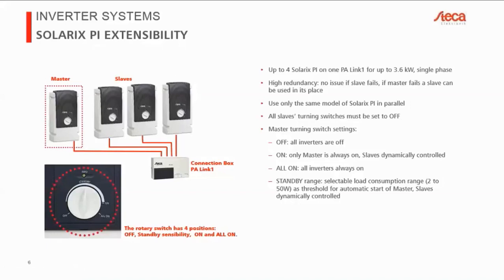Of course, the downside of having all the inverters running all the time is that you will have the no-load consumption of all the inverters as well. So if each converter is taking 6 watts, for example, then you have 24 watts of consumption because all 4 are running all the time.